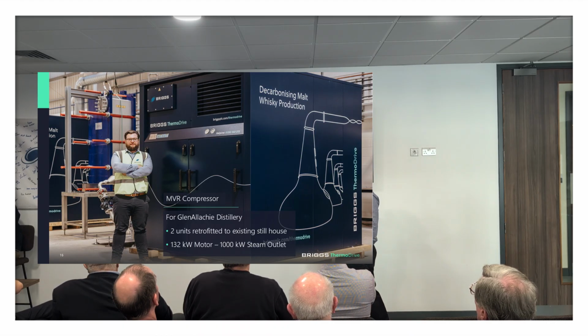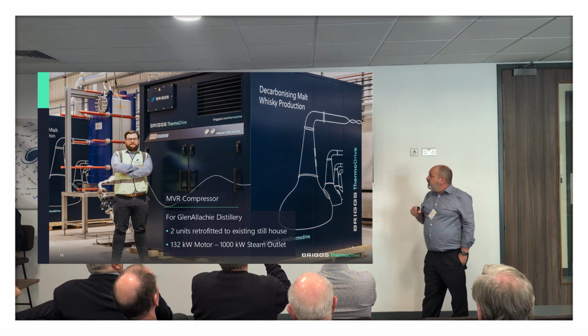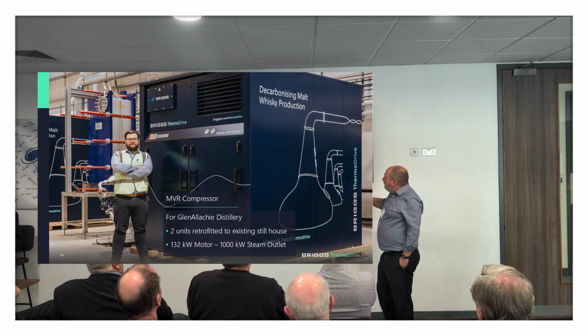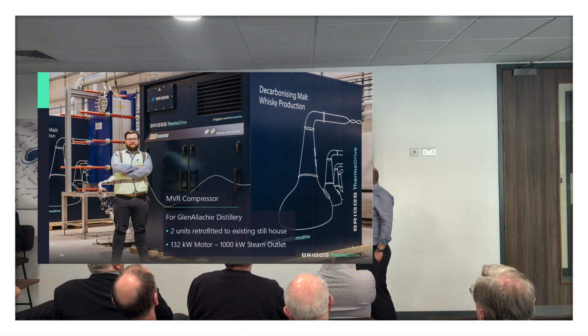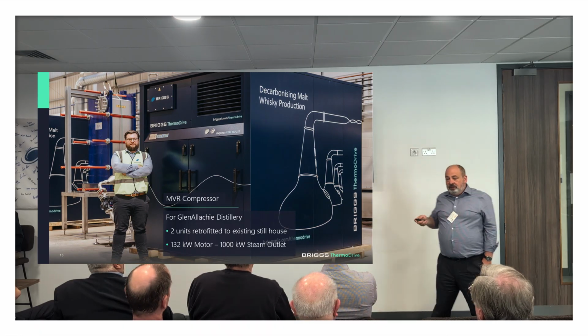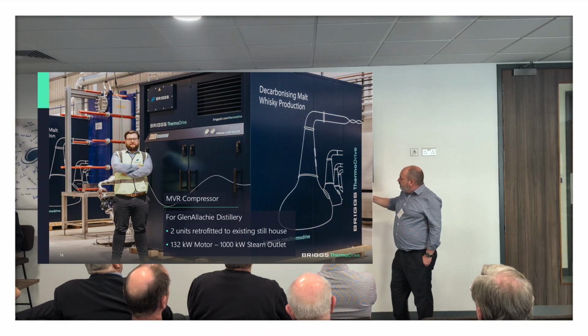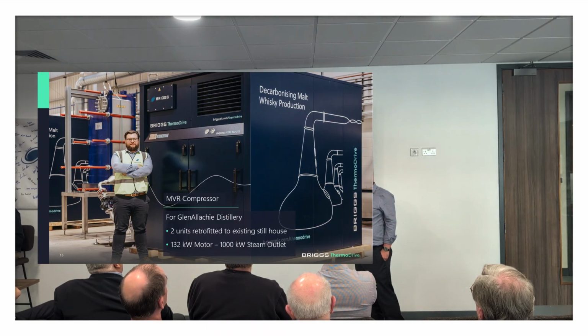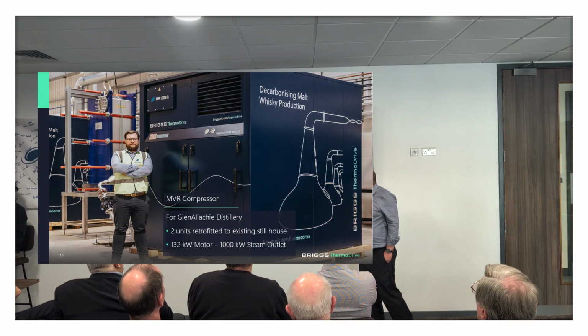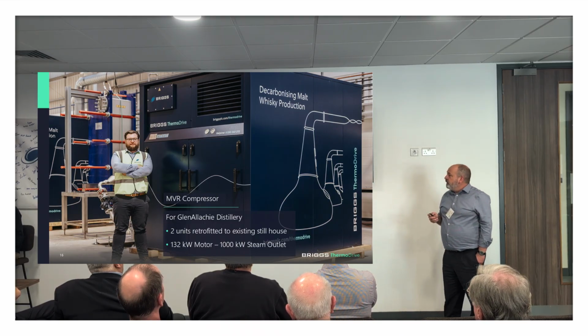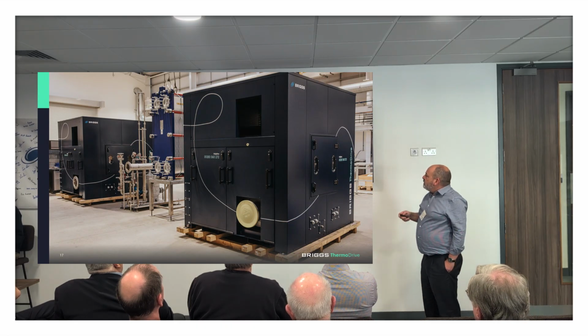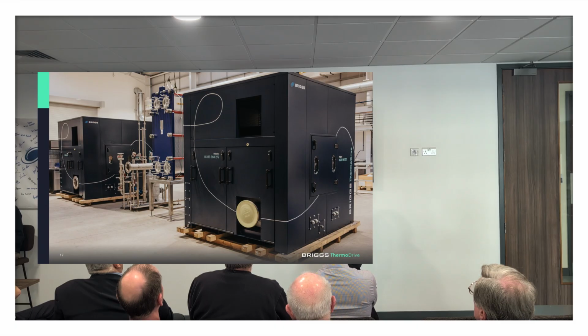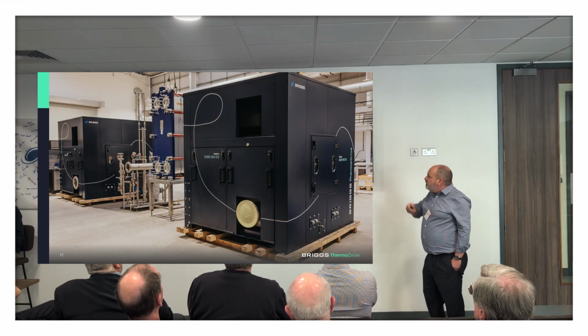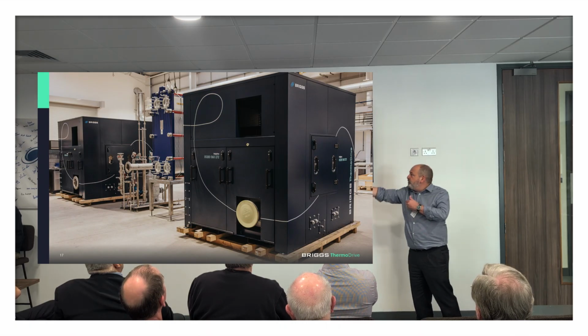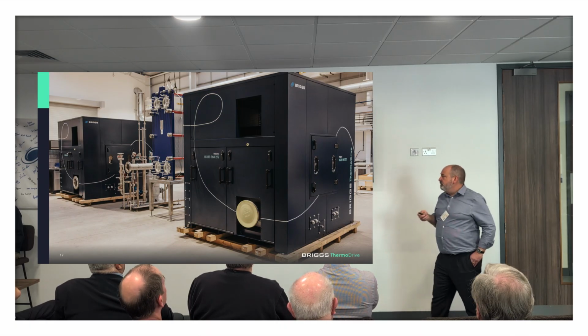So inside this unit is a 132 kilowatt motor. Quite a big, substantial motor, but that motor is generating a megawatt of steam. With variable speed drives, we'll ramp that down as the COP increases towards the end of the run, so the electrical demand will drop off, but the motor rating is 132 kilowatts. You see the 2 units. For scale, the external plate heat exchanger gives us that extra area, which means we don't have to boost the pressure so much, so the efficiency of the system is slightly better.